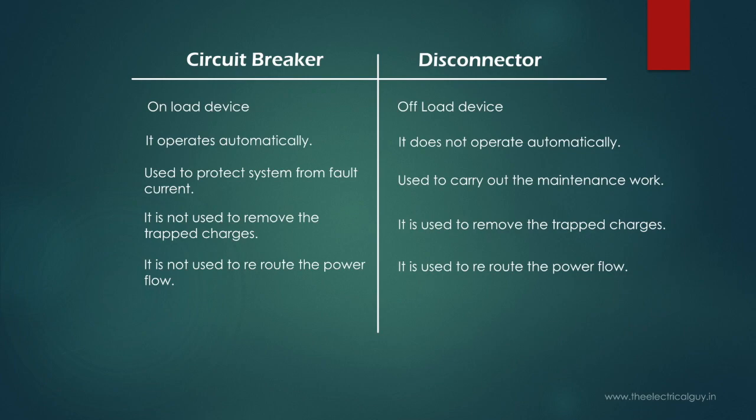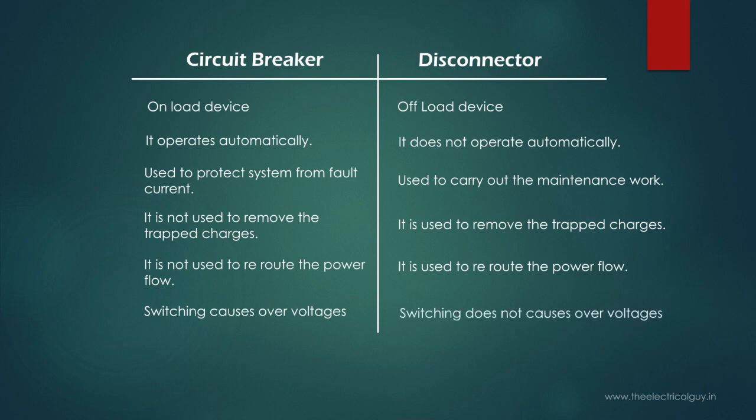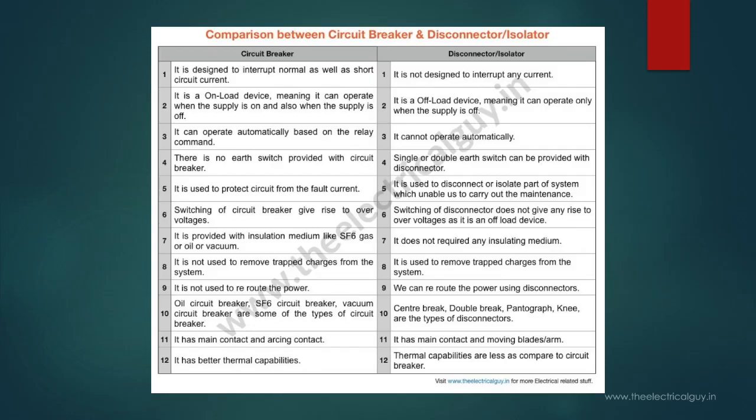One more difference in the circuit breaker and disconnector is that circuit breaker's closing and opening operation causes over voltages in the system. But disconnector operation does not cause any over voltages in the system as it is an offload device.